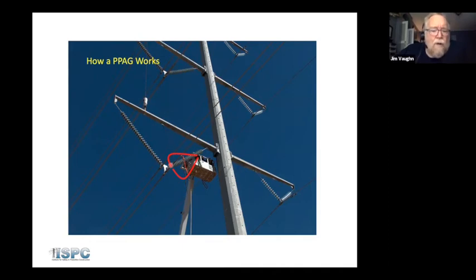We have a normal collapse of voltage up the insulator, and then we have some additional insulators in the string to provide for surges and to provide a measure of buffer over that string. Now, the possibility is that you may be on the outside of the normal collapse of voltage, but a TOV occurs and this whole string can flash over.